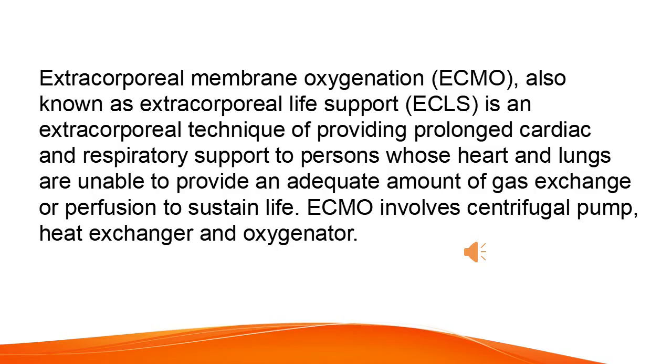Extracorporeal membrane oxygenation, ECMO, also known as extracorporeal life support, ECLS, is an extracorporeal technique of providing prolonged cardiac and respiratory support to persons whose heart and lungs are unable to provide an adequate amount of gas exchange or perfusion to sustain life. ECMO involves a centrifugal pump, heat exchanger, and oxygenator.